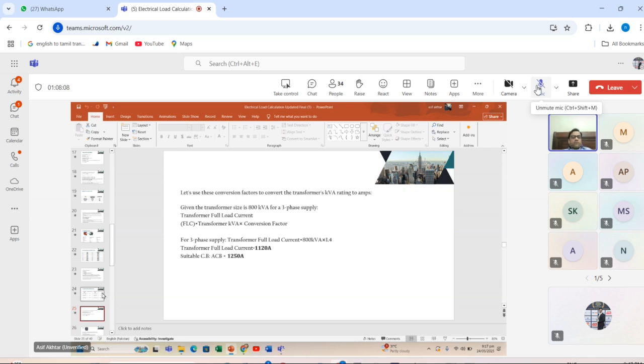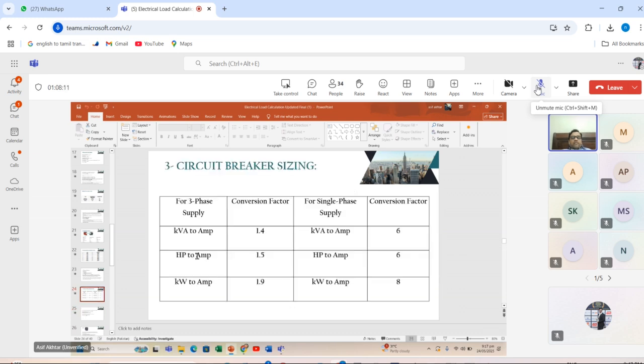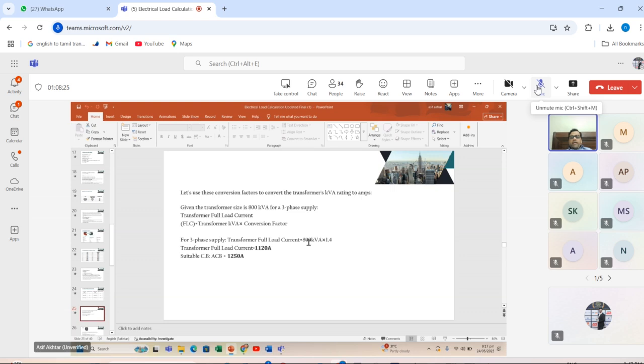Where is the 1.4 coming from? kVA to ampere, 1.4. We have an 800 kVA transformer, 800 kVA multiplied by 1.4. I will show you where 1.4 is coming from in my next slide. Once we multiply 800 into 1.4, we get a load current of 1120 ampere. So this is the total load the transformer can handle. Now we will select the ACB for this transformer. We know that there is no ACB for 1120, so we will use the ACB for 1250 ampere.